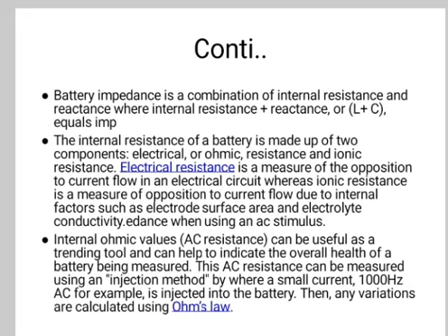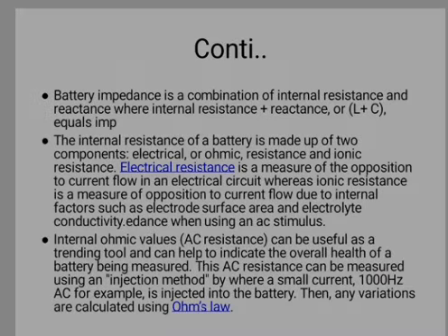It has an electronic component due to the resistivity of the component material and an ionic component due to the electrochemical factors such as electrolyte conductivity, ion mobility, speed of electrochemical reaction, and electrode surface area. The measurement of internal resistance of the battery is a guide to its condition, but it may not apply at other than the test conditions.